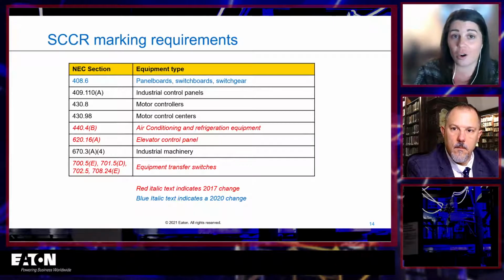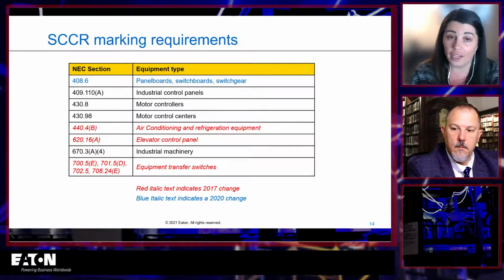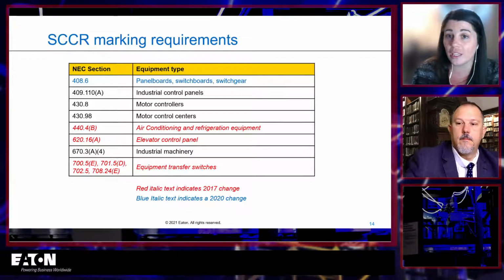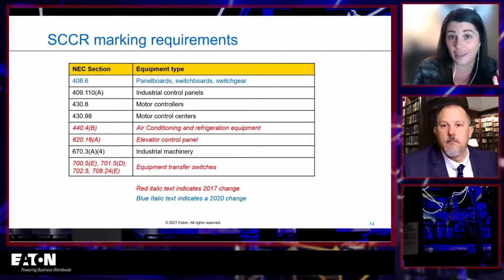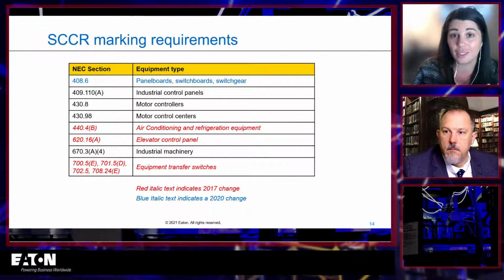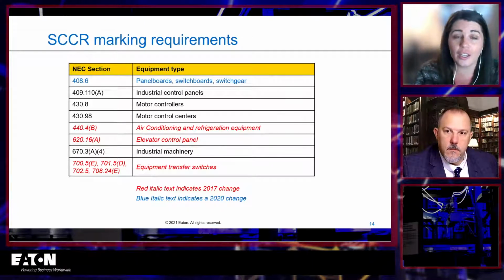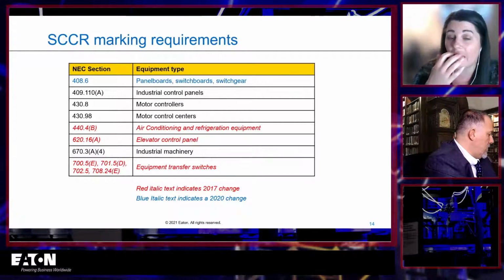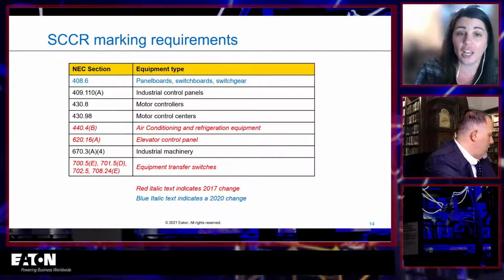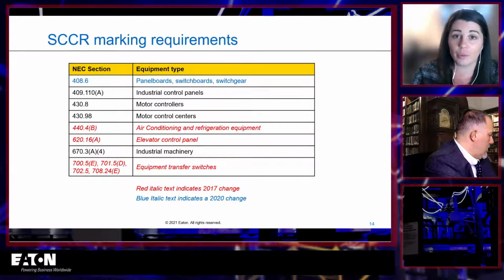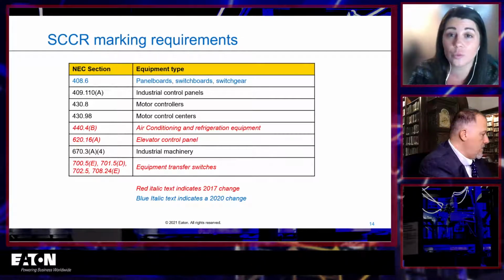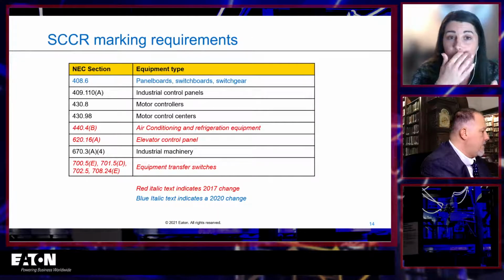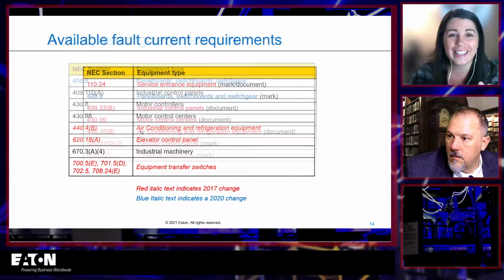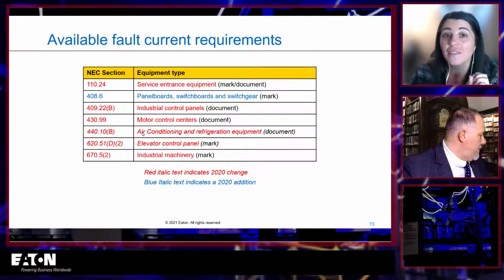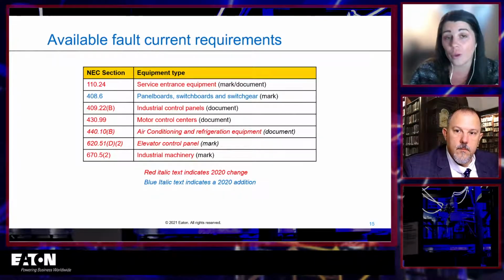So here are all of the different types of equipment per the NEC that are required to have the short circuit current rating listed on it. Now, most of these are not even news because the UL nameplate for all of these pieces of equipment would tell you that the short circuit current rating has to be on there, but the NEC added it, and you'll see transfer switches are a little bit different than everything else, and we'll talk about them specifically in this presentation as well. So yes, they made some additions saying it has to be marked on there, but what's really different is the requirements to know and document your available fault current. So if you go to the next slide, Tom, you'll see all the different types of equipment that now have some sort of requirement for you to know what the available fault current is.